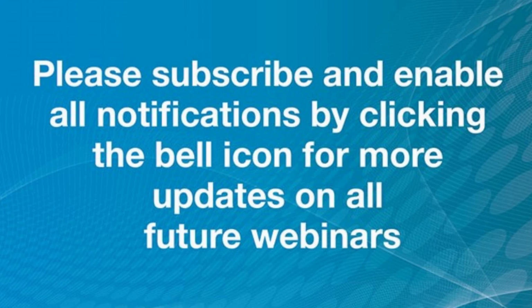Yeah, sure. There are a number of different morphological parameters that you could apply in this case. There's a particular filter that we have pre-built into the software called the S-factor filter that, I believe, was published in a paper. And I think that uses a measurement of circularity and a couple other factors to differentiate between silicon oil and protein aggregates.